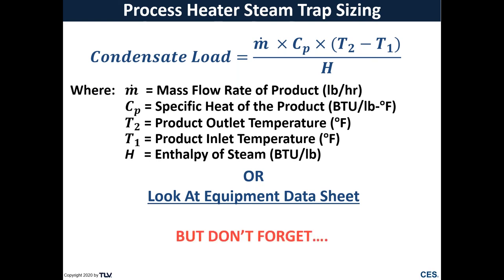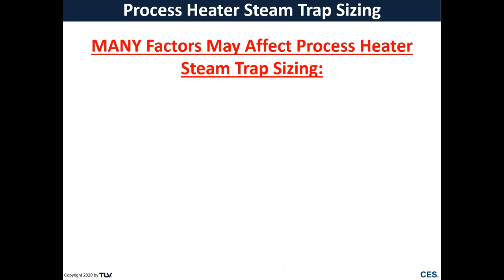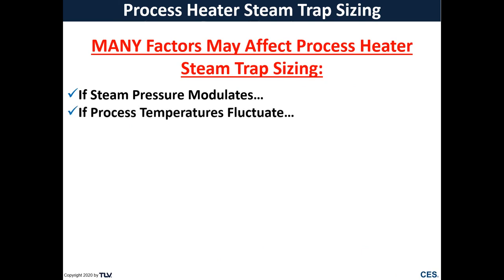But it's more complicated than that. There are many things that we cannot forget when sizing and selecting a steam trap for a process heater. So we need to consider things like, is my steam pressure changing with my product conditions? And is my process temperature fluctuating at all? Or do I have seasonal changes in this heat exchanger running different loads in the winter versus different loads in the summer?